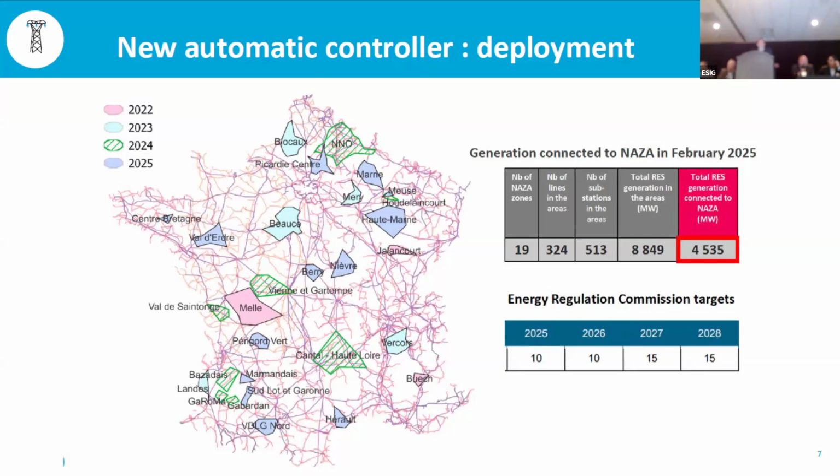gigawatts in the system, and the system doesn't necessarily need to control everything to be effective. So all of the generation is not available as a lever. Reconfiguration also usually is not needed on every breaker or every possible configuration. Usually a couple of breakers are enough to deal with the usual way to reconfigure the system.